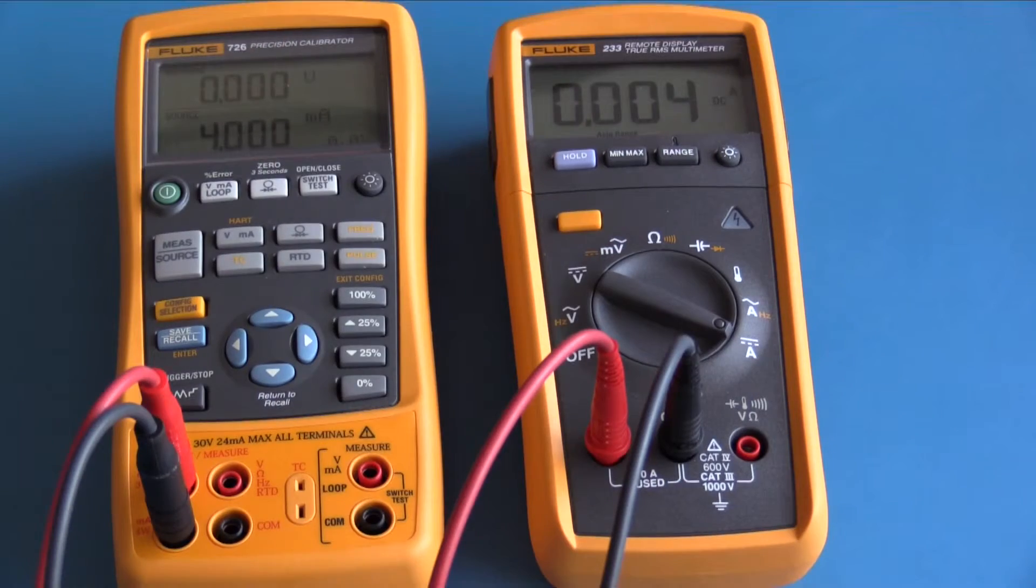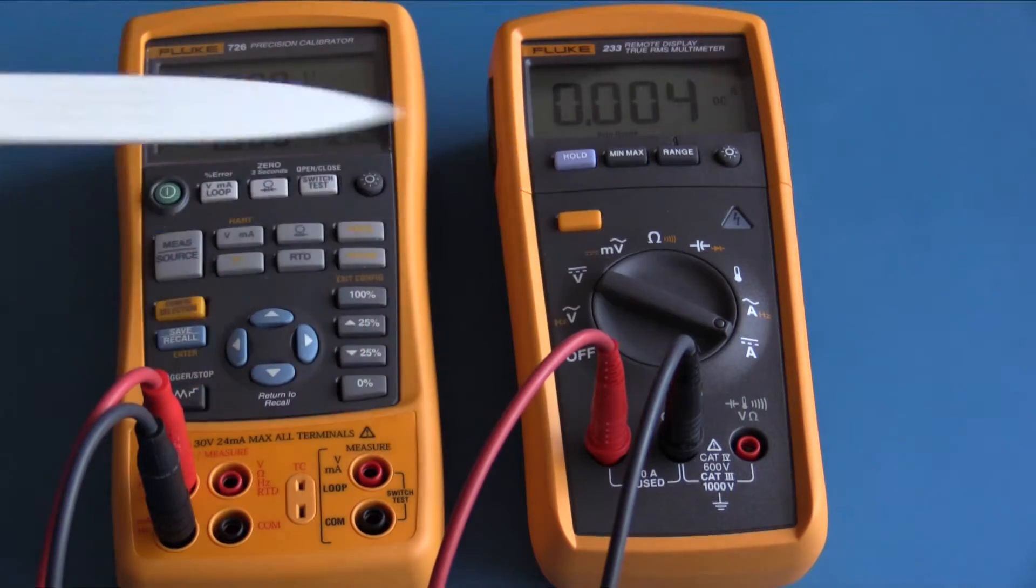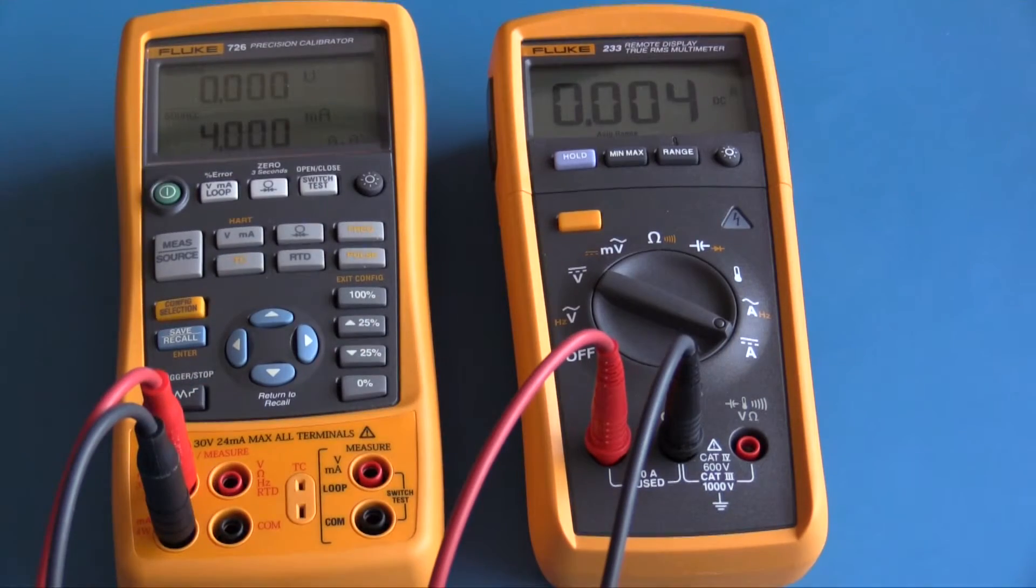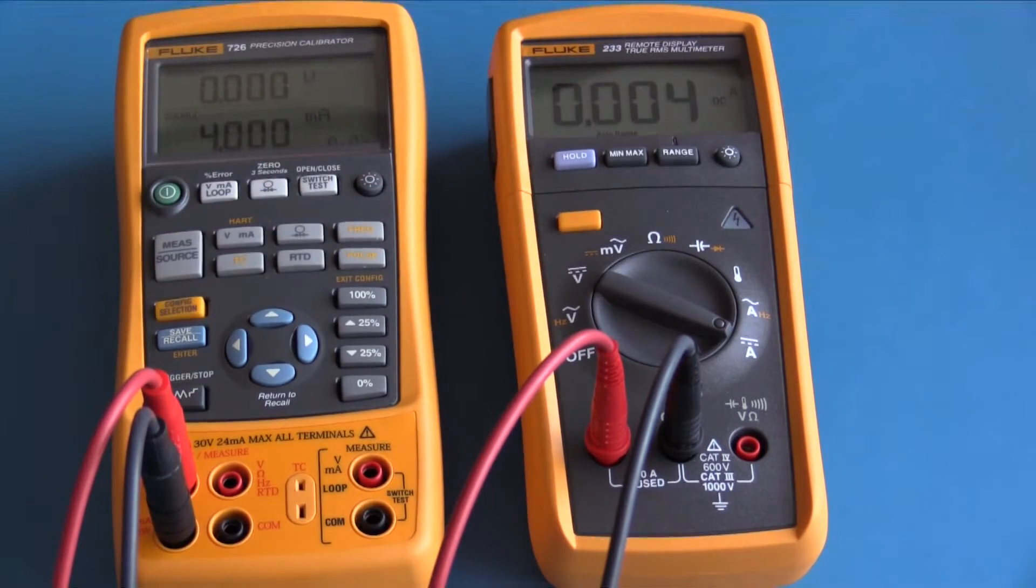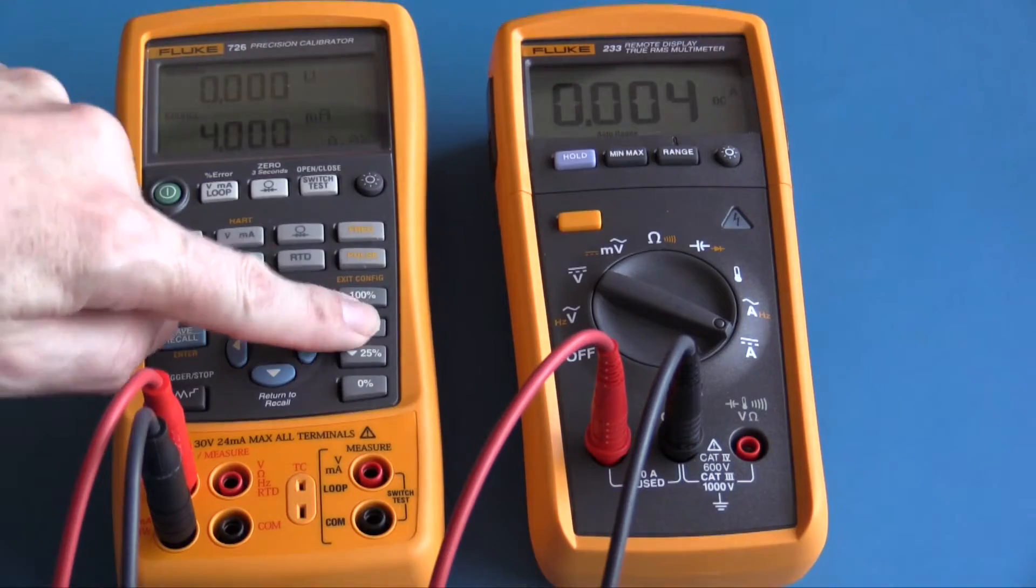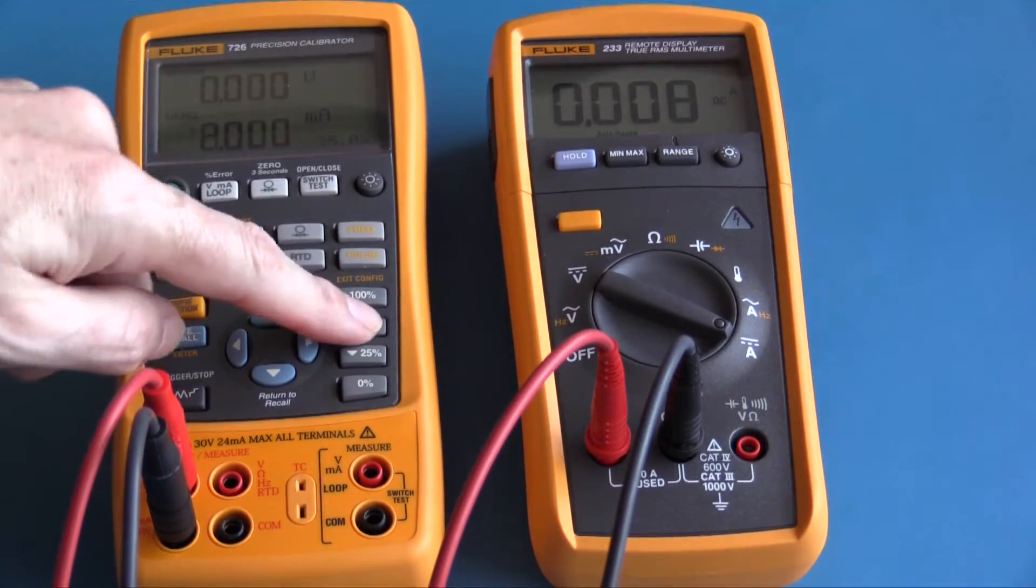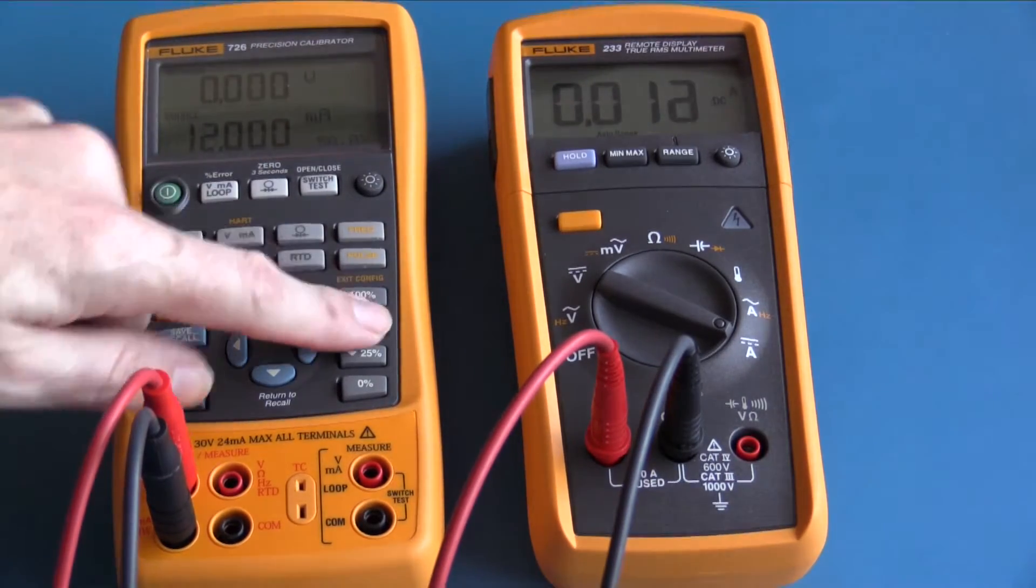To demonstrate amps, I have selected DC amps. My Fluke 726 is set up to source 4 milliamps. The Fluke 233 is showing 4 milliamps. This is at the end of the Fluke 233's milliamp range. Its resolution is only 1 milliamp DC. This is 8 milliamps, 12 milliamps, 16 milliamps, and finally 20 milliamps. Although we're at the limit of the Fluke 233's measurement capability in milliamps, it is still quite accurate.